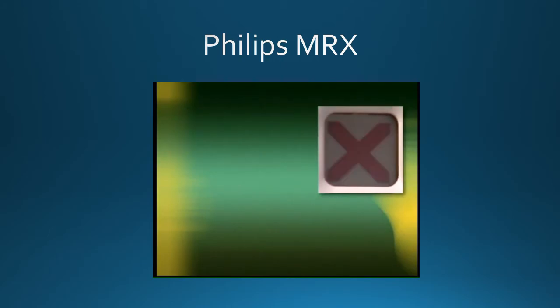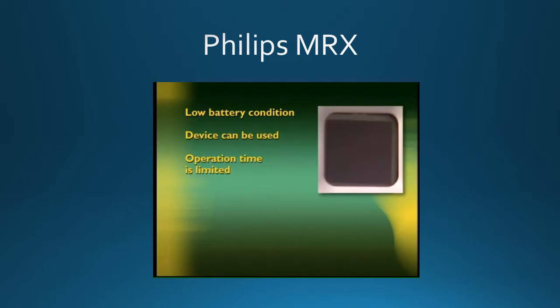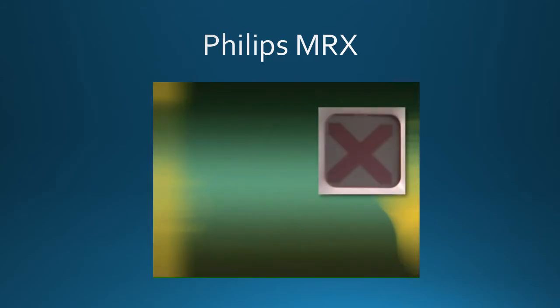A blinking red X and a periodic audio chirp indicate a low battery condition. The device can be used, but its operation time is limited. If a battery is inserted and charging, the audio chirp is not present. A solid red X and a periodic audio chirp indicate a failure has been detected that may prevent the delivery of defibrillation therapy, pacing, or ECG acquisition. A device error message will display at power on for the first failure detected.